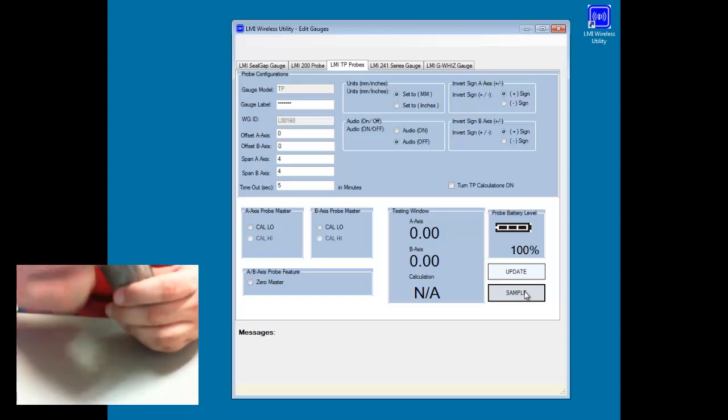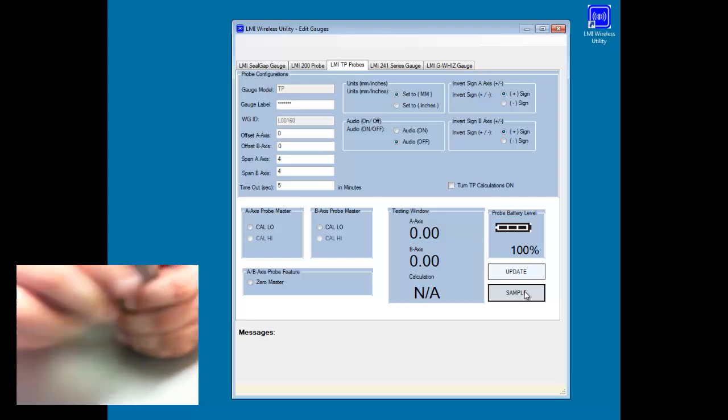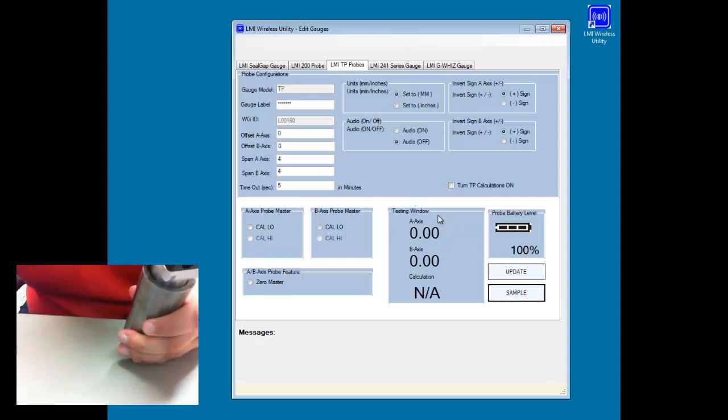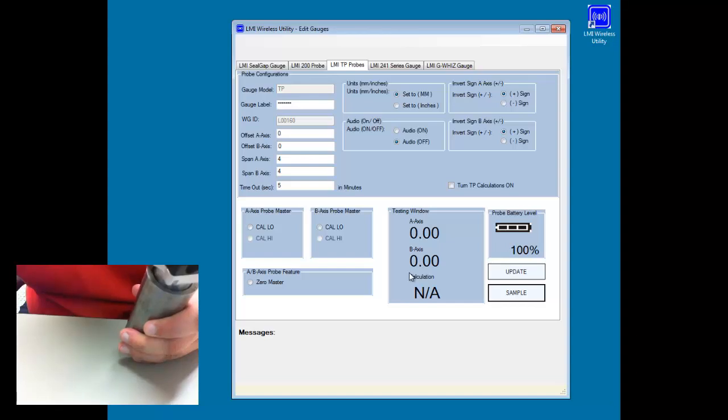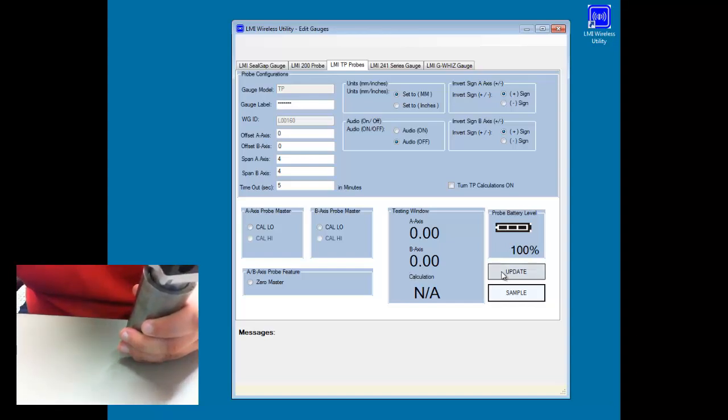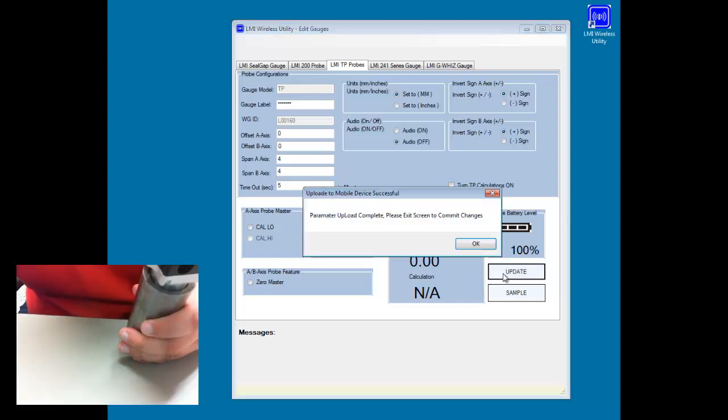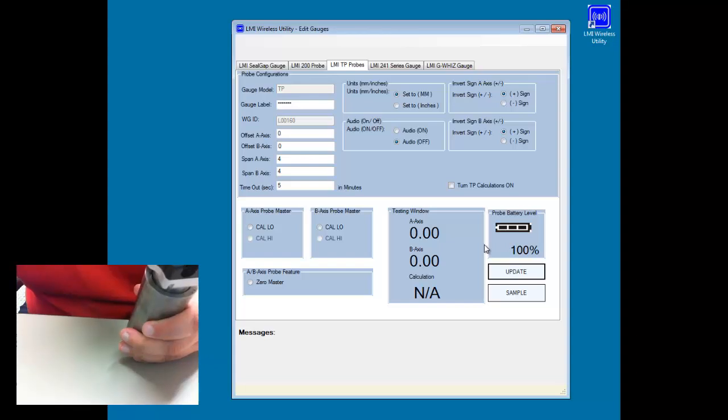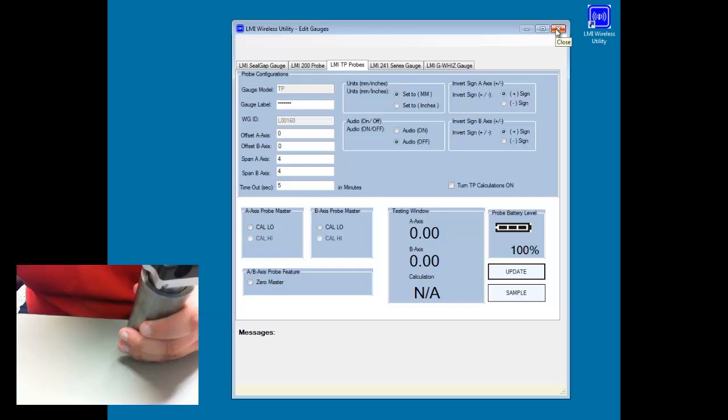Once I do that, calibration is then complete. And you should see in the testing window here that we now have zero for the A axis and zero for the B axis. The last step we need to do is click on the update button to send this information from the base back down to the probe. And once we do that, we can close out the window using the red X.